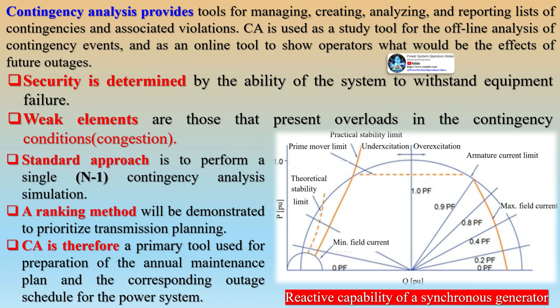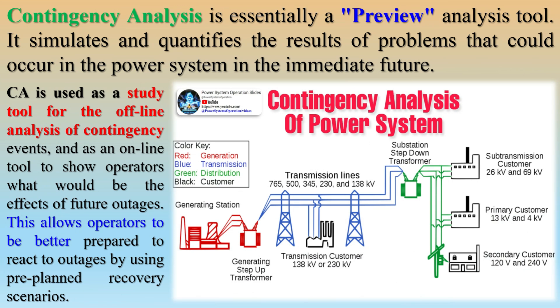The offline analysis to predict the effect of individual contingencies is a tedious task as a power system contains a large number of components. Practically, only selected contingencies will lead to severe conditions in the power system. The process of identifying these severe contingencies is referred to as contingency selection, and this can be done by calculating performance indices for each contingency. It is well known that a power system is a complex network consisting of numerous equipment like generators, transformers, transmission lines, and circuit breakers. Failure of any of these during operation harms system reliability and leads to outages.